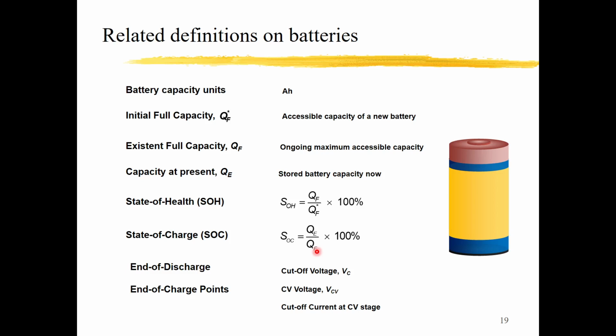For the SOC, if you fully charge your battery, then the SOC is 100%. And when you use up all the energy in your battery, then the SOC will become 0%. So the battery will experience 0% to 100% SOC in a short time, but for the SOH, maybe the SOH of your battery is 90%. If we say 90%, that means if you fully charge your battery, then the maximum accessible capacity is only 90% of its initial state. And usually SOH decreases as your used cycles increase.